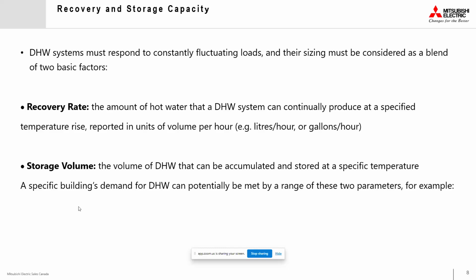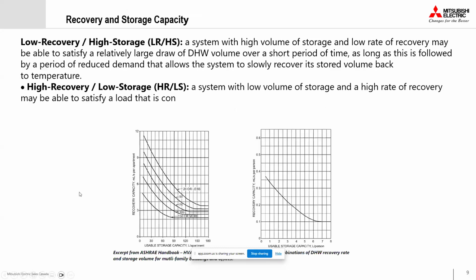And once we are supplying to the building, it's 120 degrees Fahrenheit to avoid any scalding or burns. A specific building demand for domestic hot water can potentially be met by a range of these two parameters. We have two types of system. Either it could be a low recovery, high storage system. In that system, with a high volume of storage and a low rate of recovery, you may be able to satisfy a relatively large hot water draw volume over a short period of time.